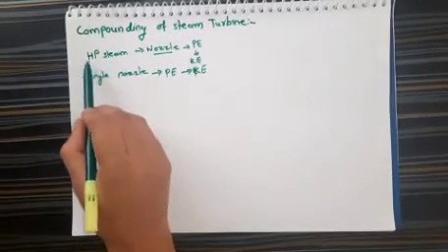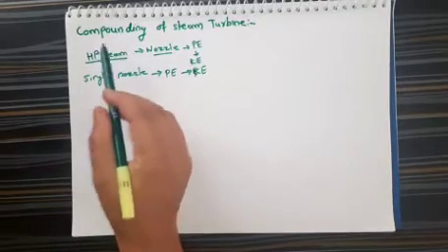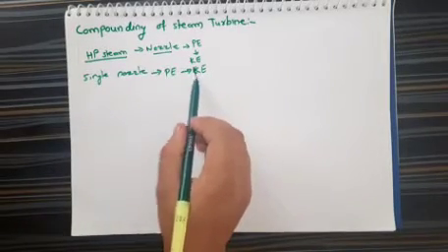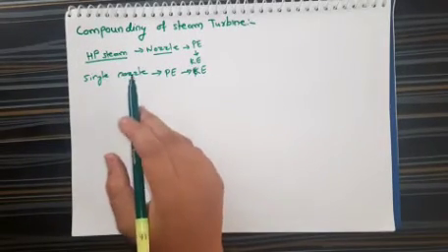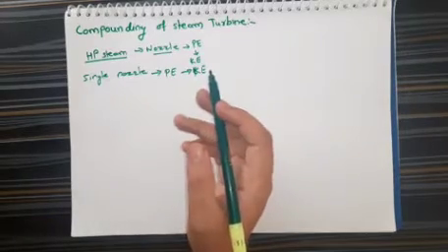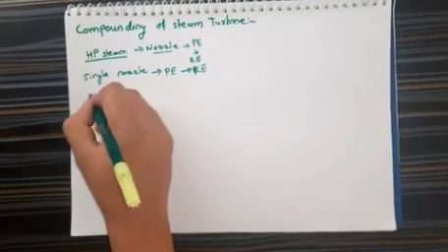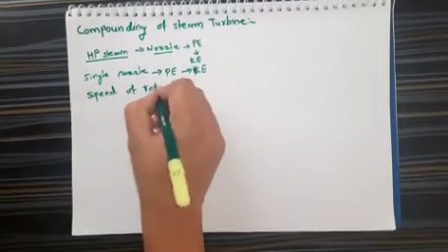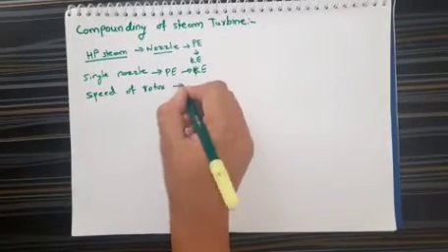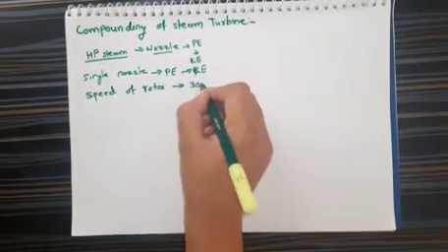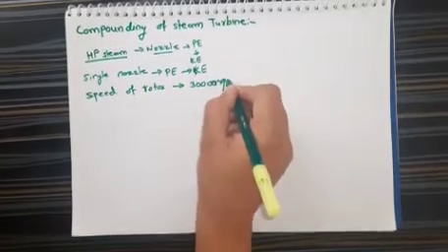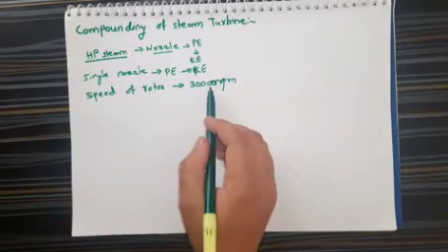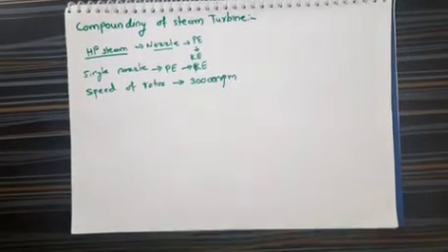As we know, the pressure from the boiler is very high, and if we allow that pressure to convert completely into kinetic energy through a single ring of nozzle, the speed of the rotor of the turbine may reach 30,000 rpm, which is very difficult to handle and impractical.